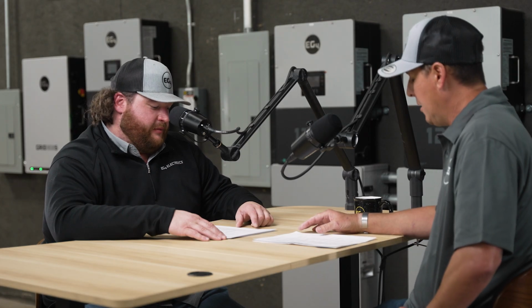So for future reference, when you're doing those kind of installs with our batteries, you're either going to want to have equal amounts of battery per inverter if you're running segregated, or if you're doing a solid battery bank, you're going to want to make sure that both of those inverters are connected to the battery bank so you get equal distribution of those loads coming out of the batteries to support those loads on the back end. So that way you don't have those imbalanced legs on your 120/240 systems. Yep, split it right down the middle in every way possible.